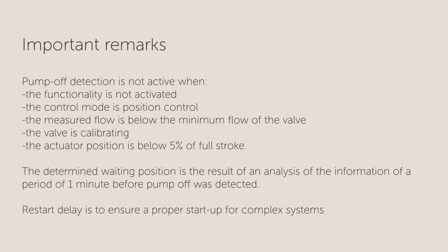So the waiting position, or the position where TA Smart will move to, is calculated during an analysis of the information 1 minute before the pump off was detected. The restart delay is clearly not a delay in control, but it is a time TA Smart will allow for the system to restart, this time patiently staying in the waiting position.